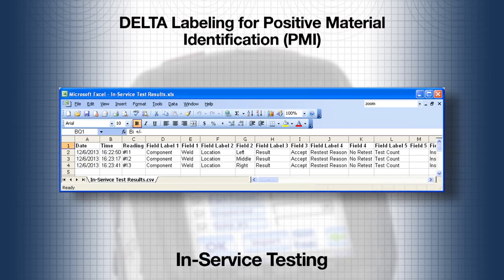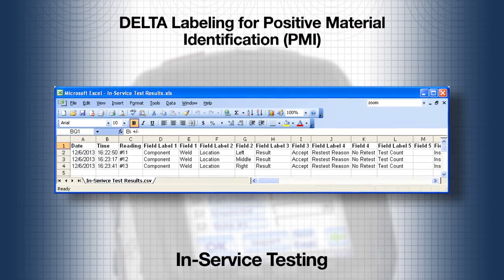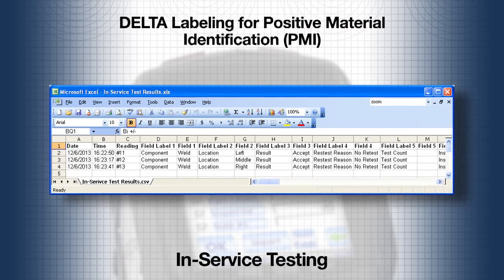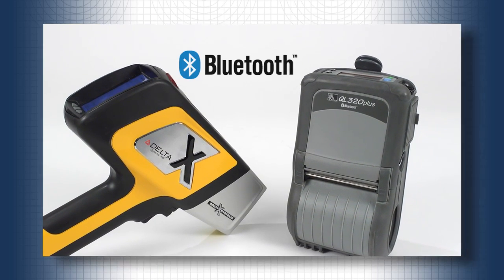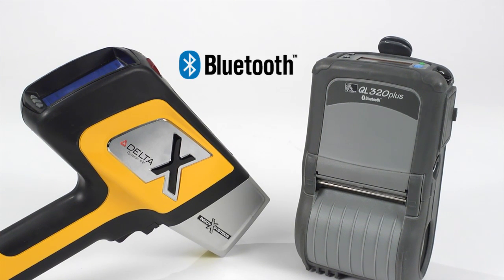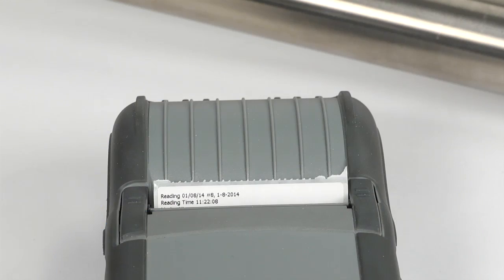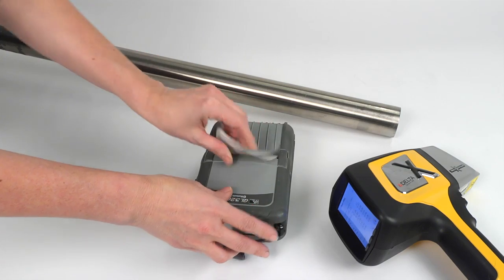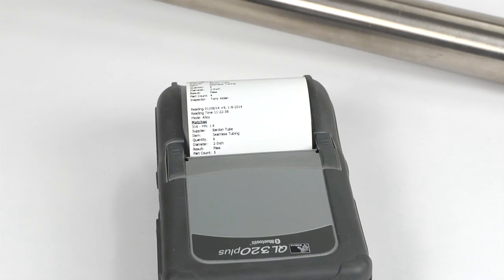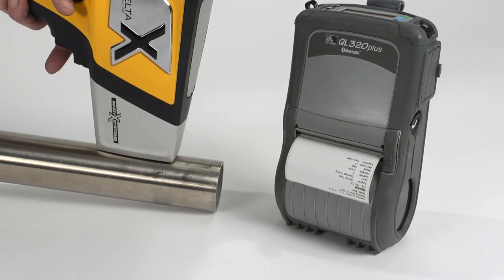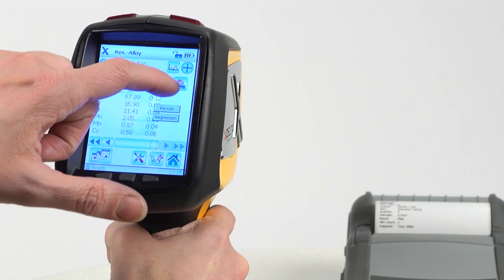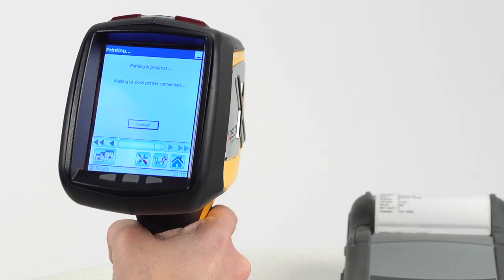The report, which can be used in any PMI software package, will show the labels and results of this testing sequence. In addition to creating a report from your test results, you can also print your test results. The Delta XRF analyzer connects wirelessly to a Bluetooth printer, which is sold as an accessory. You can print to a label to immediately identify components tested, or print to receipt-style paper to include with other documentation. You can print results as soon as the test is taken, or choose specific tests to print after testing is complete.